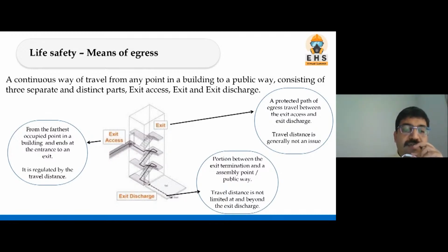Exit is very clear for us. For example, our office is built in a building, and the staircase we use is the exit. But the area from where you are sitting up to the staircase entry is called exit access. You must have heard the term travel distance - travel distance should be only 15 meters, not more than that. So the travel distance pertains to the exit access, wherever your workstation is, up to the entry of the staircase.